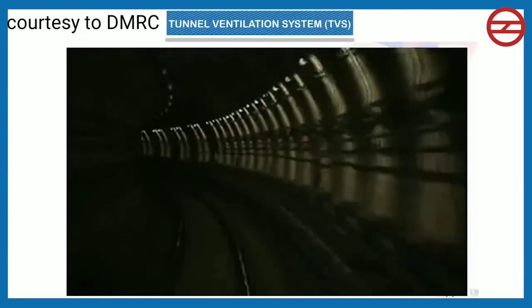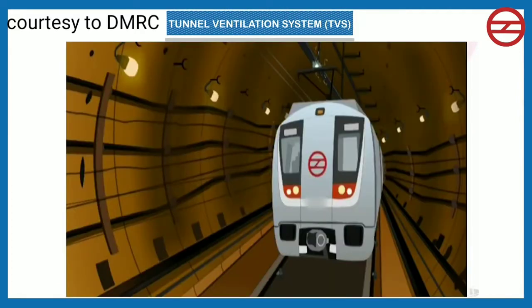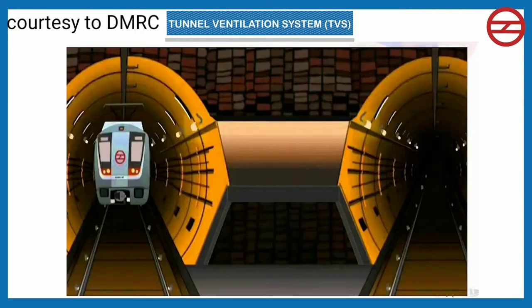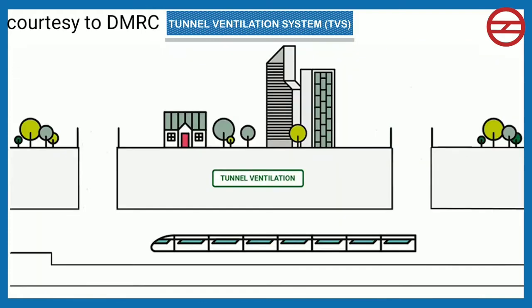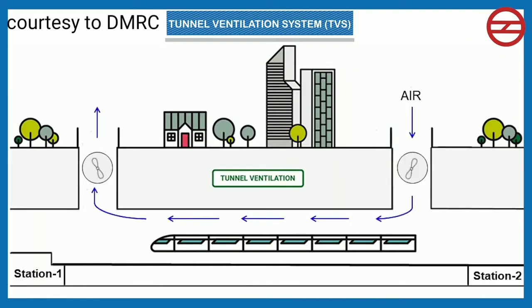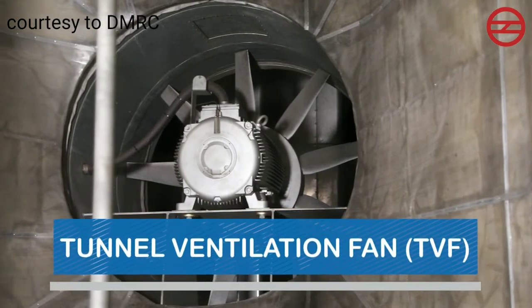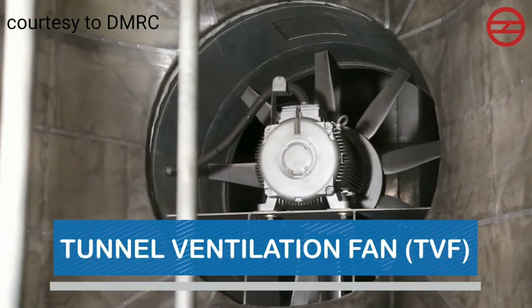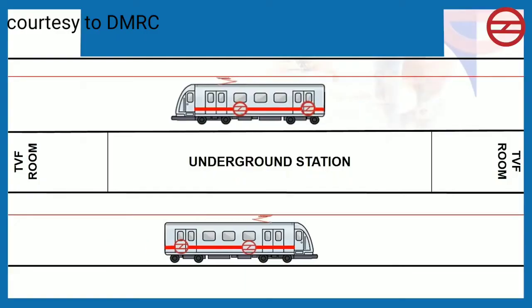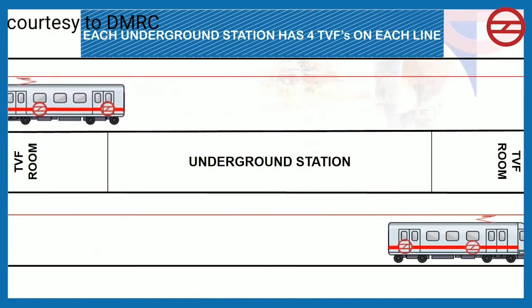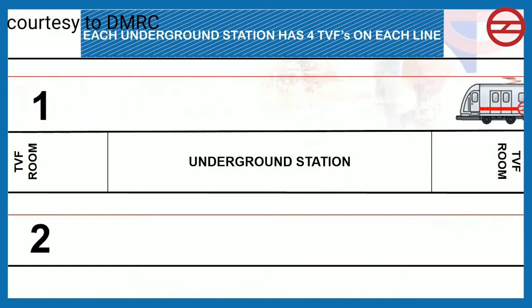Tunnels in underground stations are also enclosed areas and may require ventilation in case of any critical situation. Therefore, underground stations are also provided with a system of ventilation inside tunnel known as Tunnel Ventilation System, that is TVS. The main component of tunnel ventilation system is tunnel ventilation fan, that is TVF. Each underground station has 4 TVFs on each line.